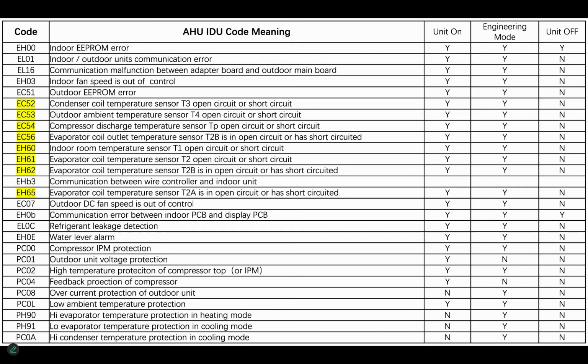Indoor fan speed out of control, basically that's just telling you that the fan either failed to reach 250 RPM or went outside of 800, and I think it's 880.